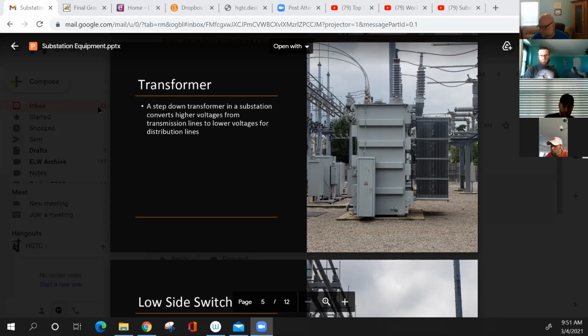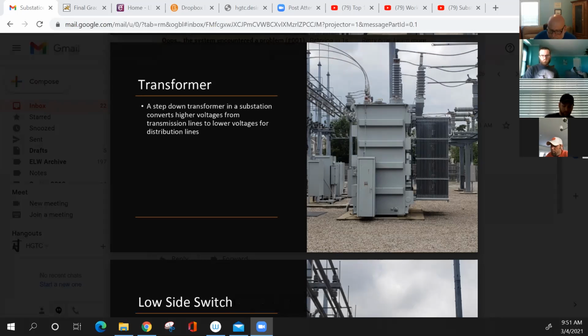So on the transformer itself, we talked about the fins for cooling, and that's for protection. It has all kinds of relays connected into this transformer that are monitored by dispatch. If they start getting alarms off this transformer, whether overcurrent, undercurrent, or overheating, they'll get an alarm and call substation maintenance.